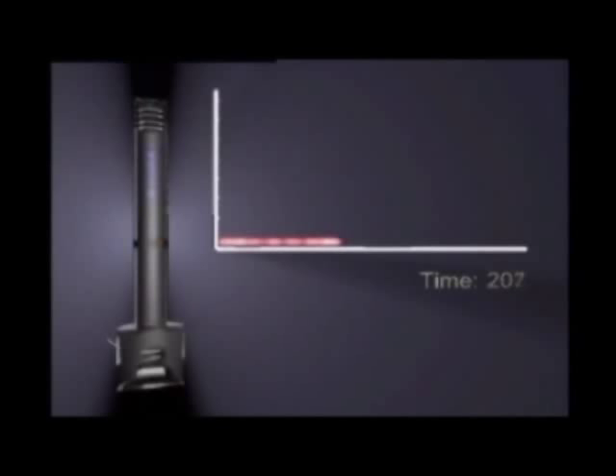The second step is the time of flight mass spectrometer phase. In the linear mode, particles would impinge on the ion detector within a few nanoseconds after ionization. Higher mass molecules will arrive later than the lighter ones. Flight time measurement makes it possible to measure molecular mass directly. Each peak in the spectrum corresponds to a specific mass of the element along the time axis starting from the ionization moment.